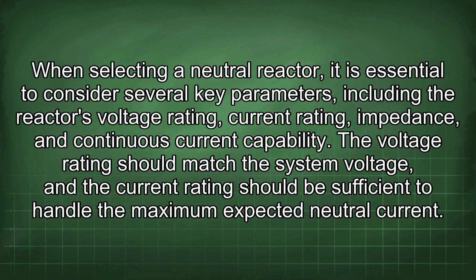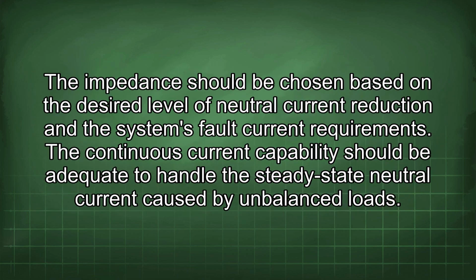When selecting a neutral reactor, it is essential to consider several key parameters, including the reactor's voltage rating, current rating, impedance, and continuous current capability. The voltage rating should match the system voltage, and the current rating should be sufficient to handle the maximum expected neutral current. The impedance should be chosen based on the desired level of neutral current reduction and the system's fault current requirements. The continuous current capability should be adequate to handle the steady-state neutral current caused by unbalanced loads.